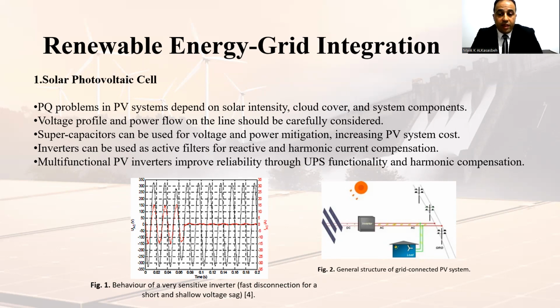The power quality problem in the PV system depends on the solar intensity, the cloud cover, and system components. Voltage profile and power flow in the line should be carefully considered. A supercapacitor can be used for voltage and power mitigation, but it increases PV system cost. The inverter can be used as an active filter for reactive and harmonic current compensation. A multifunctional photovoltaic inverter improves reliability through UPS functionality and harmonic compensation.